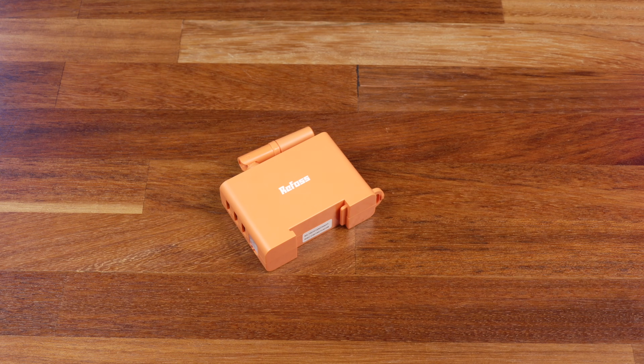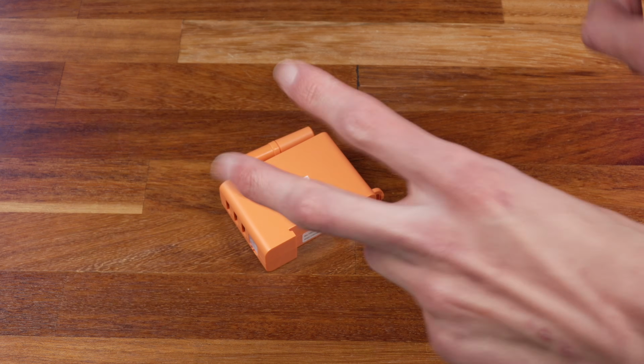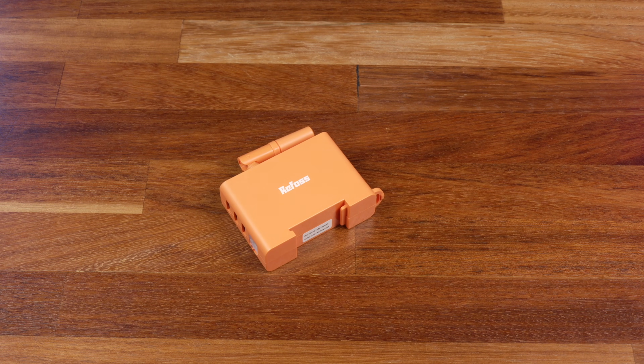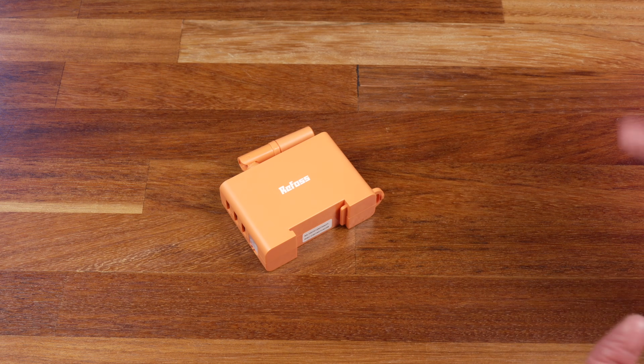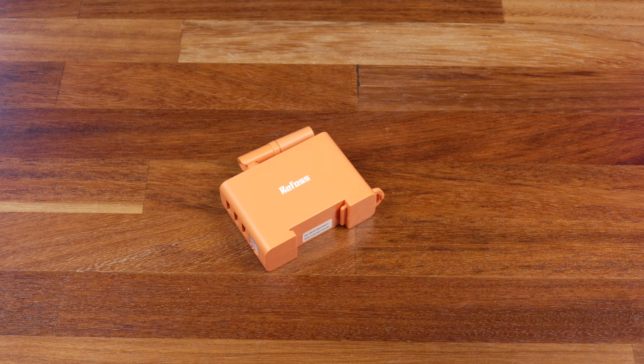Here in the UK, our regulations are pretty strict when it comes to installing things in a consumer unit, and it generally comes down to what's known as type testing. The idea is that the manufacturer of the consumer unit will have tested it with all of their own devices, MCBs, RCDs, RCBOs, and all that sort of stuff. And a large part of that testing relates to how those devices all contribute to and withstand the temperatures inside the board. Especially things like MCBs, circuit breakers, they're thermal devices. They heat up, and then when they heat up too much, that's when they trip. So the temperature that they output into the board and the temperatures in the board around them can very much adjust the tripping characteristics and things like that.